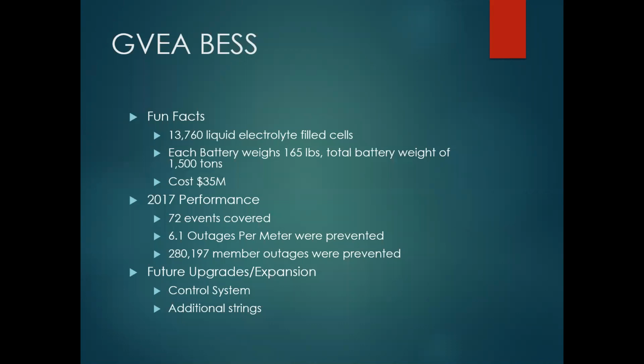Once a year at least, the battery manufacturer runs what they call a state of health, looking at resistance degradation and such, the whole chemistry of the battery, to see where we're at on that lifespan. Two of the strings are actually newer. They are right around 65% state of health. It's kind of a qualitative way of saying it, right? And the other ones are pushing more down in the 25% range. So we're going to be at a point where a decision will have to be made on upgrading these, and that may or may not affect this additional string discussion, right? Potentially we could upgrade our two older strings and prolong life.